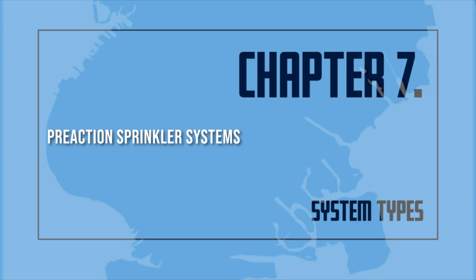A supervisory device signals when the valve is opened. The pre-action valve can also be operated manually. The pre-action system has several advantages over a dry pipe system. The pre-action valve opens sooner because the fire detectors react to heat changes faster than sprinkler heads. Fire and water damage may be decreased because water is sprayed on the fire more quickly.